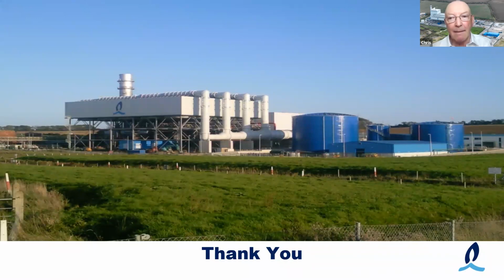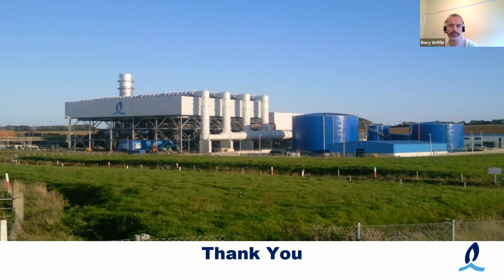So yeah, we can switch seamlessly at 180 megawatts from gas to distillate. If you were to push up, you need to bring in your water injection then to suppress your NOx emissions. For the unit to switch back from distillate to gas, we can't do that at our minimum stable. So we have a derogation with the grid. We actually have to drop down to approximately 25–30 megawatts on the gas turbine. And when the fuel rate is lower on the distillate, at that point, then you can switch to the gas fuel and bring it back up.